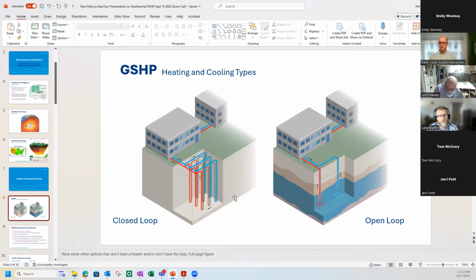in this graphical simulation. So there are two types of ground source systems. One is called a closed loop system, where you're drilling 300 to 500 foot deep boreholes, grouting them with a thermally enhanced grout, which for us geologists means that there's just more quartz sand in that grout mix than typical, because it's more thermally conductive. And then to heat a building, you'd run very cold fluids down through that 1-inch diameter HDPE U-bend loop. And second law of thermodynamics, we're trying to extract heat from the ground, soil or rock, into that fluid, and then we'll bring that fluid back up at a greater temperature. So if we put fluid down at 32 degrees in the U-bend pipe, it'll come back at 37 degrees.